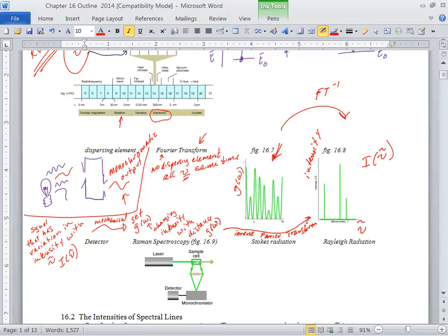So what's moving as you get this? What's this x-axis? What's the physical thing that's moving with that FTIR? The mirror, right? The mirror's here, measures the intensity. The mirror moves a little bit over here, measures the intensity. Moves here, measures the intensity. So there's a really nice stepping motor in there. You can't even see little dips or anything. It's very smooth. That's probably why it's so expensive.